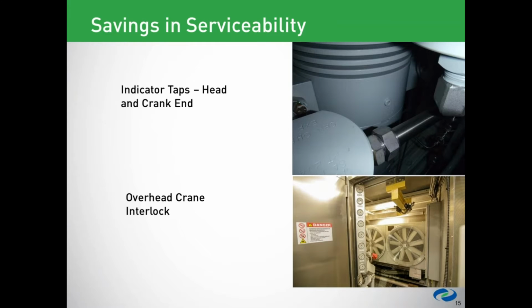The third item is indicator taps that are drilled into the compressor cylinders of every unit that ships out of our factory. This provides easy instrumentation access to the compression ports if required. If there is a service issue in the field, it's very easy to take our instrumentation package, plug it in, see what's happening, and see what the issue might be, allowing for quick addressing of those issues and less downtime. So, Brad, just to key on that, you don't even have to turn the unit off to do that, do you? You would have to turn the unit off, yes. Okay. Just to drain out the pressure that's residual in those ports. Okay. But quick process, yeah. Very quick process.